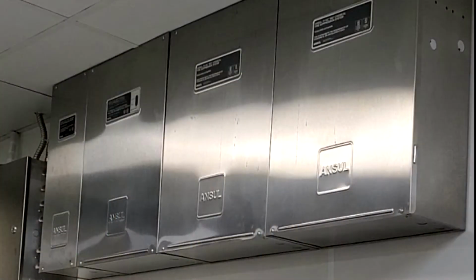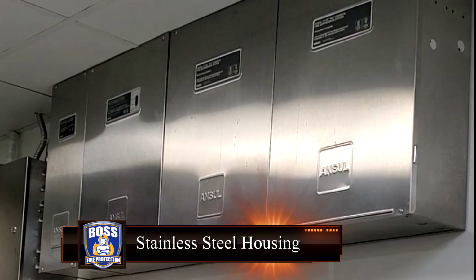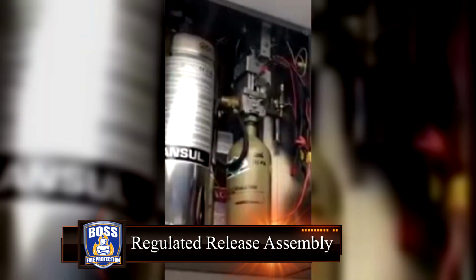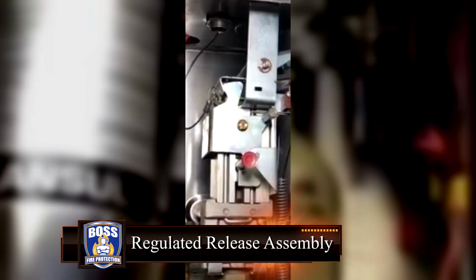In each fire suppression system, the control head, bottles, and cartridges are typically stored in a stainless steel housing cabinet. This is where you will find the regulated release assembly. The regulated release assembly is the main component of your fire suppression system. This combination of components is what triggers the fire suppression system to release wet chemical agent in the event of a fire. The regulated release is made up of the following components.